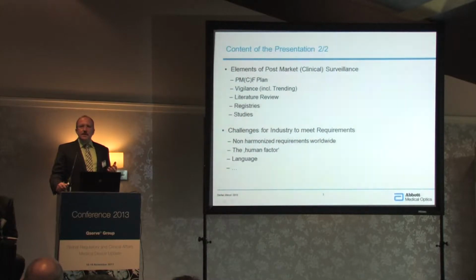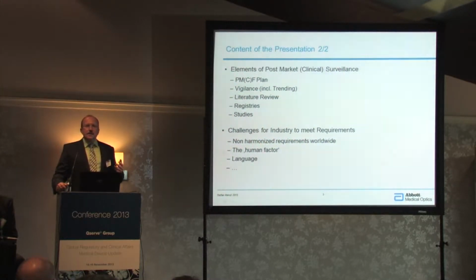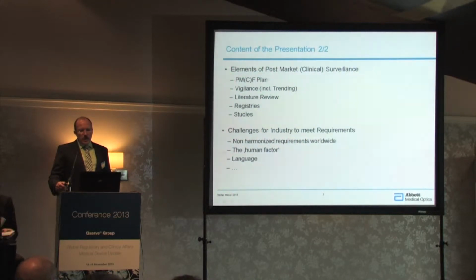And then, of course, there are also so-called post-market studies with CE-marked devices in Europe, to see how the product really performs in the market when it's used more broadly, not only by a selected group of experts that you might involve in your pre-market trials, but also by doctors who are not so experienced with this type of use of the device or the procedure. Finally, I also want to touch on some challenges for industry in meeting all those requirements, especially with a look beyond Europe into the international environment, because the requirements are not all the same.